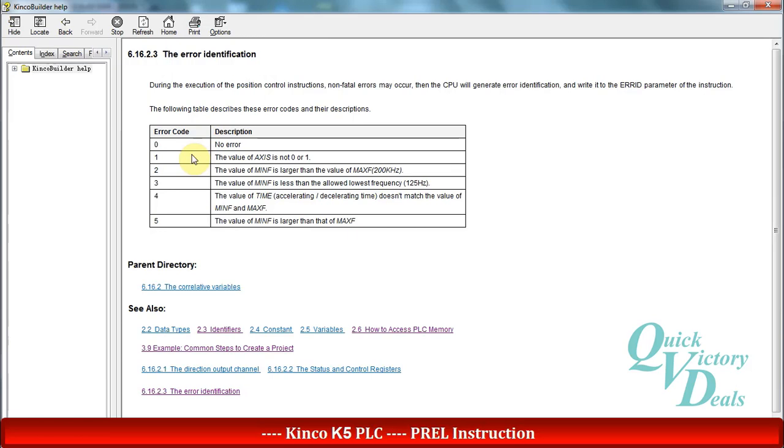Before discussing error code number 2, please pay attention that in K5 CPUs the maximum frequency in Q0.0 and Q0.1 is 200 kilohertz. So error number 2 means that the min-f is larger than maximum frequency or 200 kilohertz.